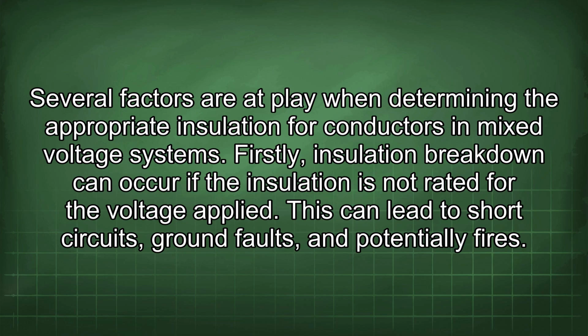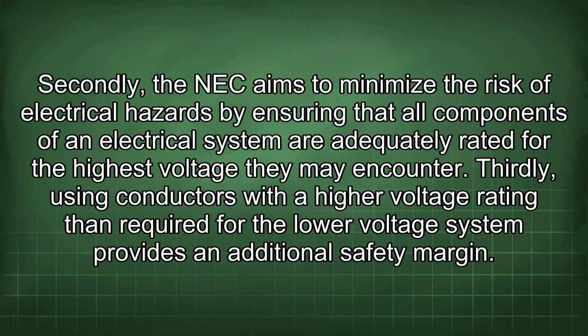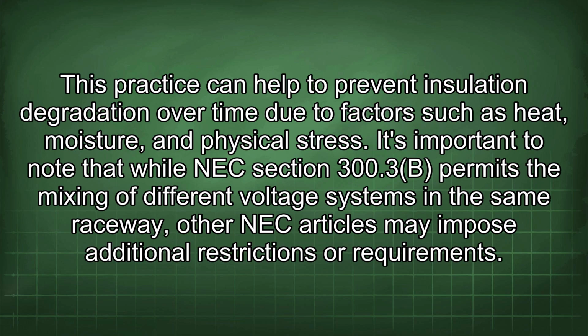Several factors are at play when determining the appropriate insulation for conductors in mixed voltage systems. Firstly, insulation breakdown can occur if the insulation is not rated for the voltage applied. This can lead to short circuits, ground faults, and potentially fires. Secondly, the NEC aims to minimize the risk of electrical hazards by ensuring that all components of an electrical system are adequately rated for the highest voltage they may encounter. Thirdly, using conductors with a higher voltage rating than required for the lower voltage system provides an additional safety margin. This practice can help to prevent insulation degradation over time due to factors such as heat, moisture, and physical stress.